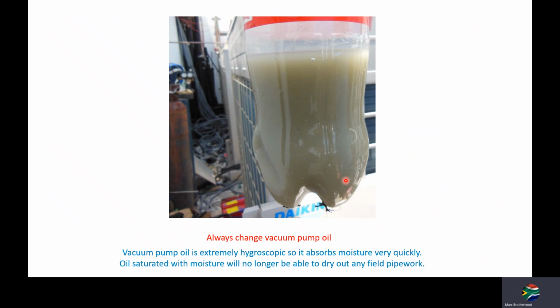A vacuum pump is purely there to lower the atmosphere and cause liquid to boil. It is not like a vacuum cleaner that sucks. It doesn't work like that. It's a boiling process. And the oil has to be of the best quality so it can absorb the moisture that has boiled off in the field pipework.